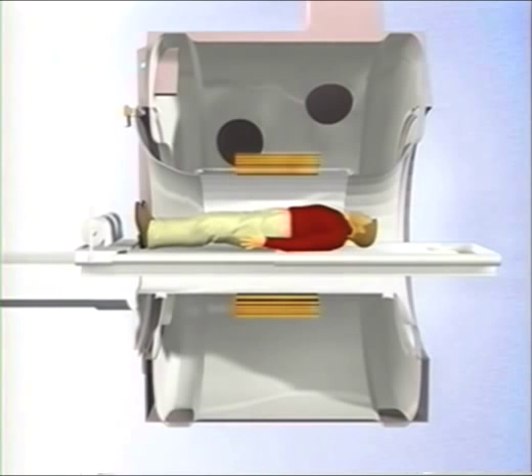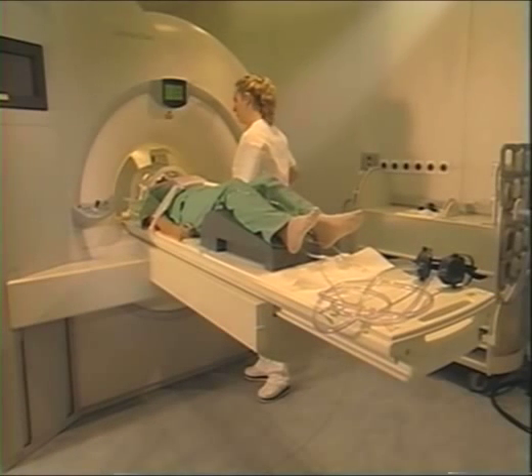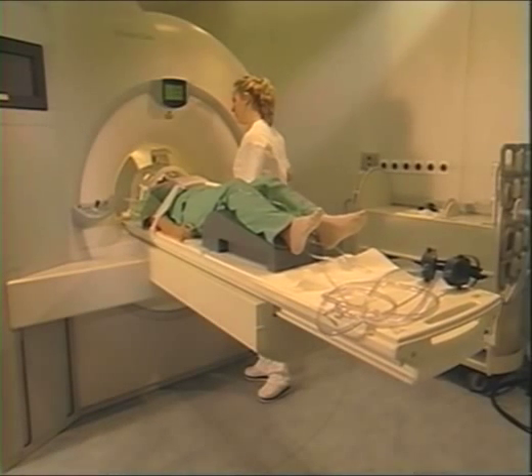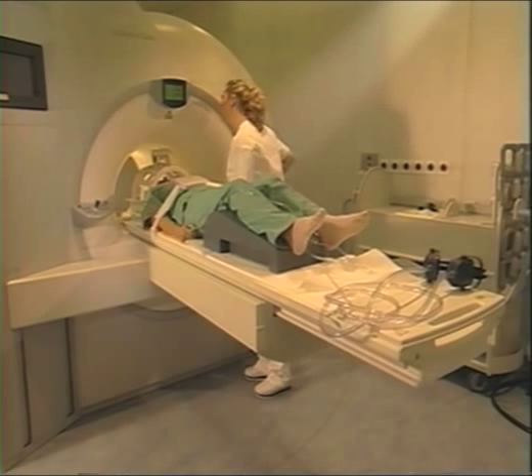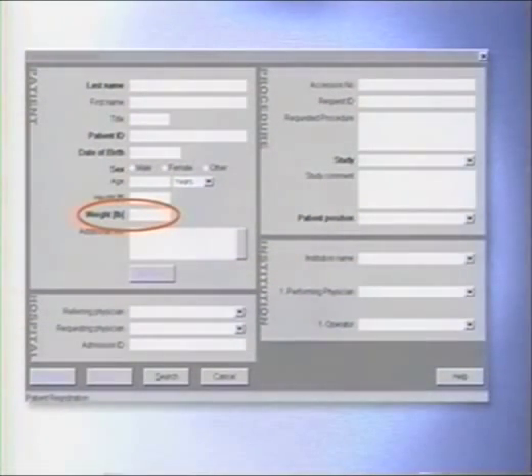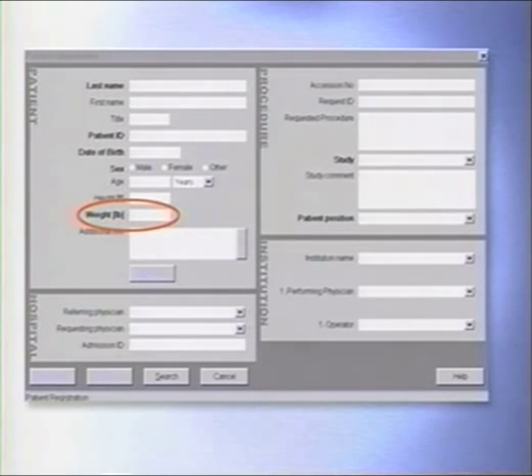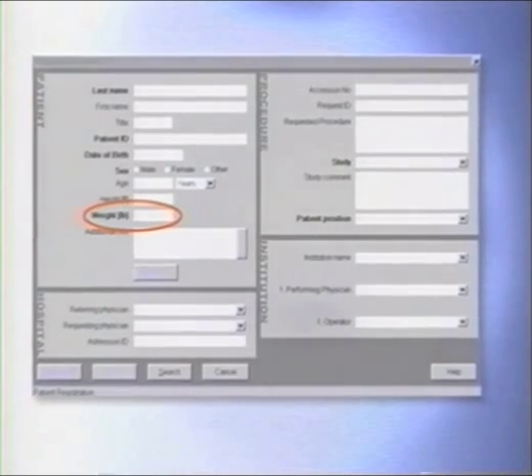The high-frequency alternating fields used for stimulating the magnetic resonance in MRI are absorbed by the body and cause the irradiated body region to warm up slightly. For safety reasons, control circuits in the MR imager prevent the energy absorbed by the body, SAR, from exceeding a predetermined limit. Since the computation of SAR involves the patient's weight, it is important to enter this information correctly during registration. The limit values are fixed by international safety standards.